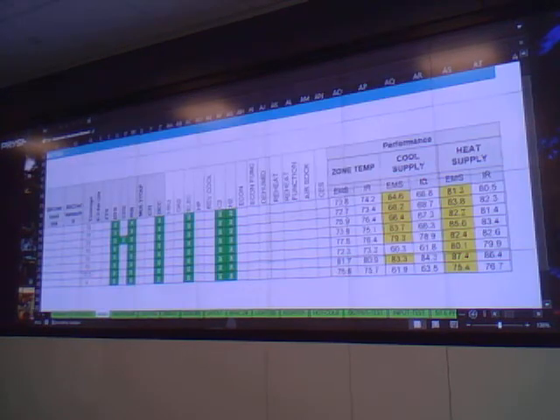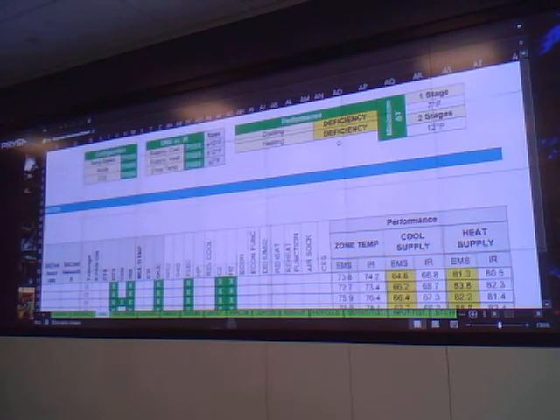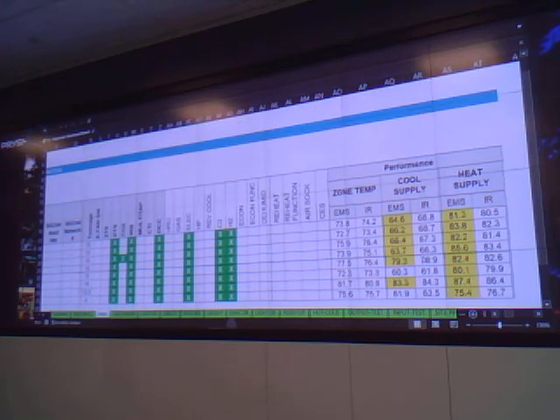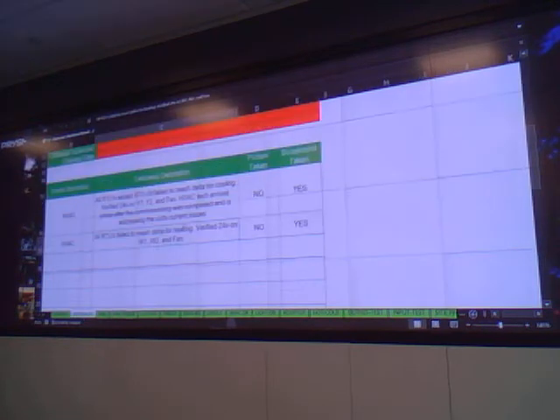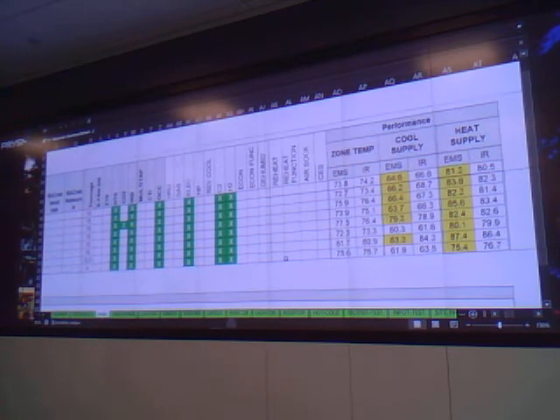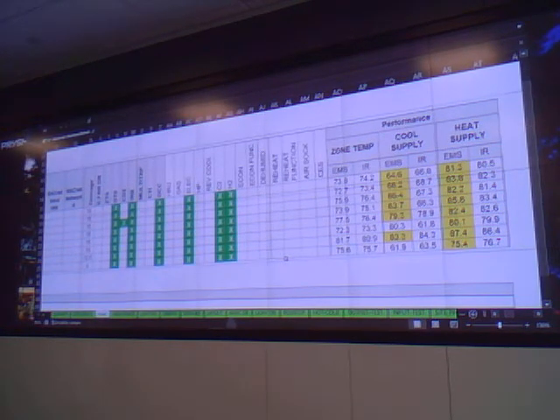So here we can see the confirmation, every one of these showed yellow for heating. None of them met their delta. It's got a deficiency that he tested on W1, W2, and fan. So thermostat sending up the right voltage, confirm that voltage at the unit. Unit's still not heating. I don't know the situation at this site, but I would assume when you see none of these units heating, gas is probably off. Be my guess.